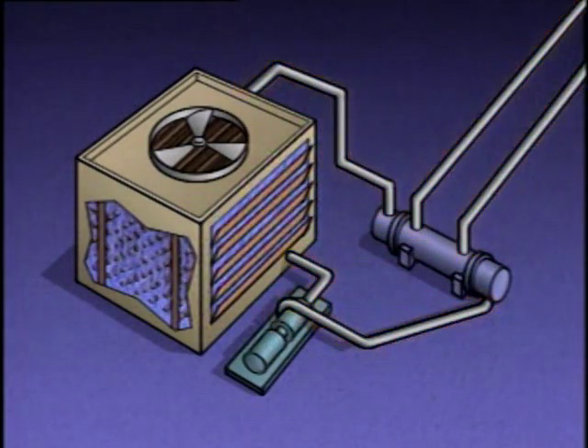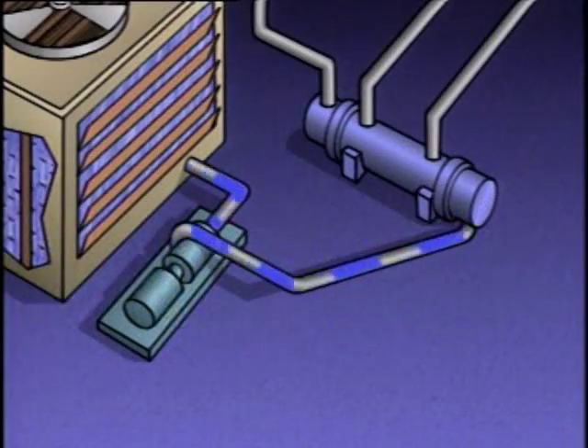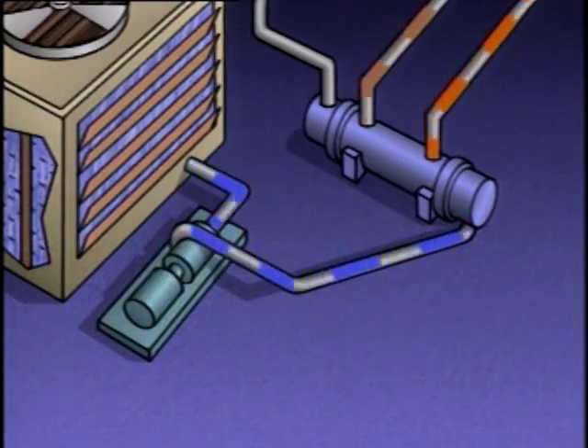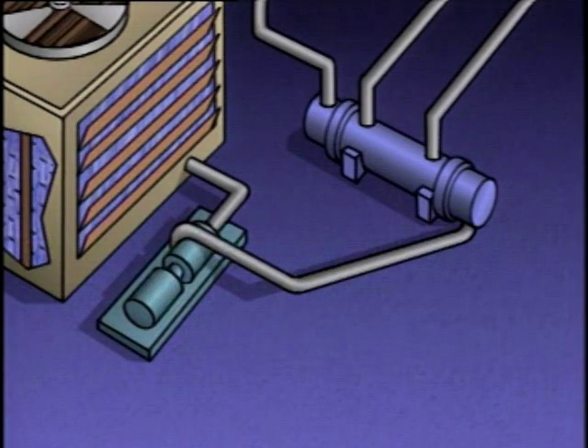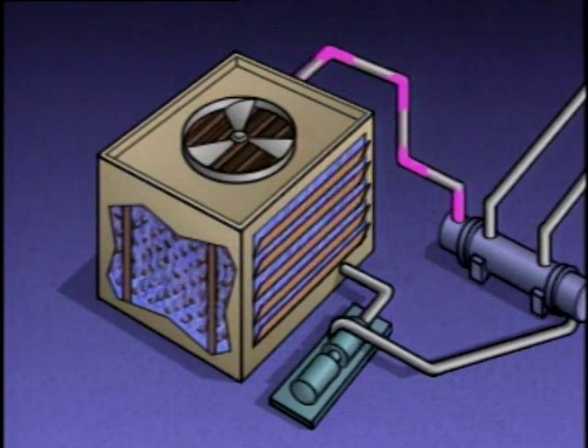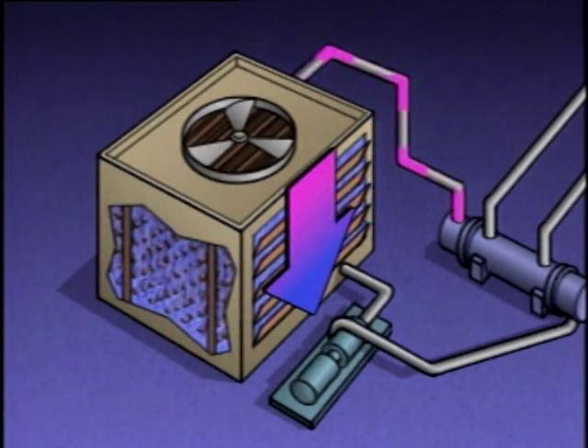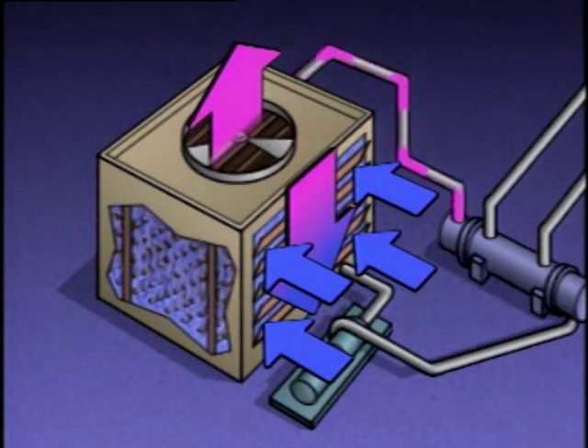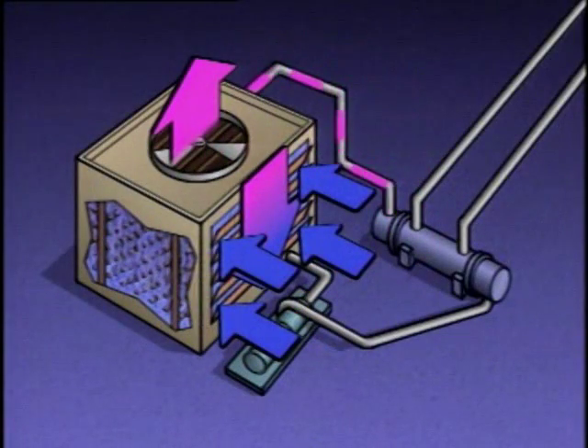In this system, cool water is pumped from the bottom of the cooling tower to the heat exchanger. In the heat exchanger, heat from a process fluid is transferred to the cooling water. After absorbing heat from the process fluid, the water flows from the heat exchanger to the top of the cooling tower. The water then falls through the tower and is exposed to air, which cools the water. The cooled water collects at the bottom of the tower and is pumped back through the system for reuse.